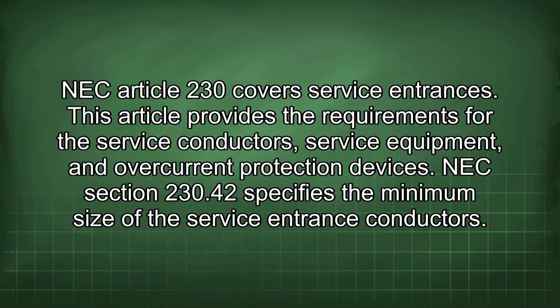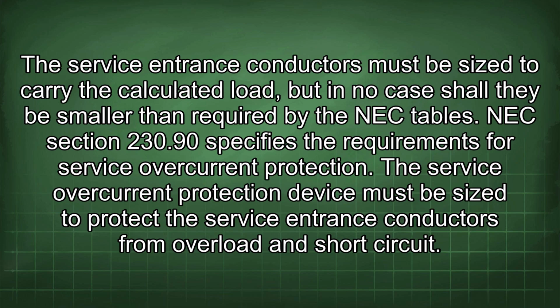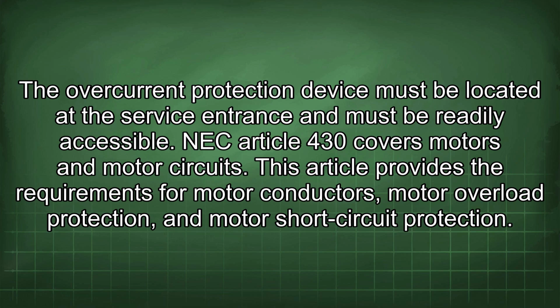NEC Article 230 covers service entrances. This article provides the requirements for the service conductors, service equipment, and overcurrent protection devices. NEC Section 230.42 specifies the minimum size of the service entrance conductors. The service entrance conductors must be sized to carry the calculated load, but in no case shall they be smaller than required by the NEC tables. NEC Section 230.90 specifies the requirements for service overcurrent protection. The service overcurrent protection device must be sized to protect the service entrance conductors from overload and short circuit. The overcurrent protection device must be located at the service entrance and must be readily accessible.